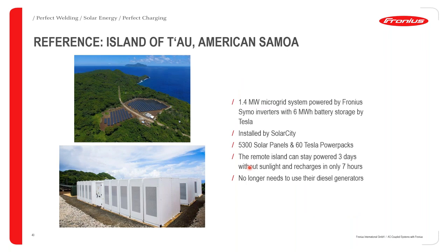Now looking at another reference, this is an island of Tau, which is in American Samoa. With this installation, they did not use the Tesla Powerwall. They used what is called the Tesla Powerpack, okay, which allows for really big systems. So please do note, if you are using the Tesla Powerwall, you can only use 10 Tesla Powerwalls in a string. That gives you a maximum storage capability of, let's say, 160 kilowatt hours. If you want to go for anything bigger than 160 kilowatt hours, you then need to look at the Tesla Powerpack, which is these big white units here in the bottom. Each of these Tesla Powerpacks is, I think, around 100 kilowatt hours storage, each of them.